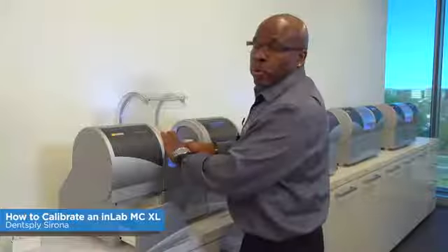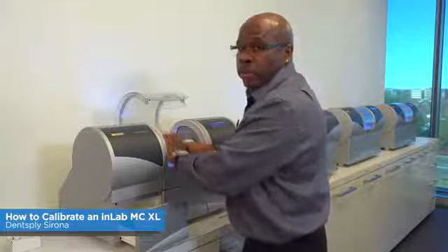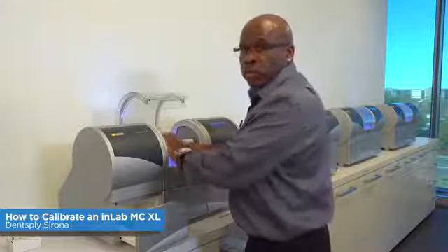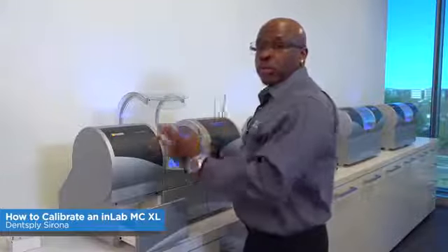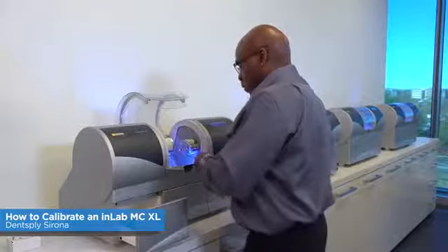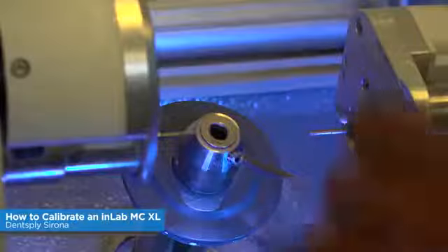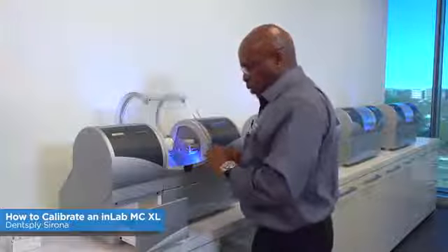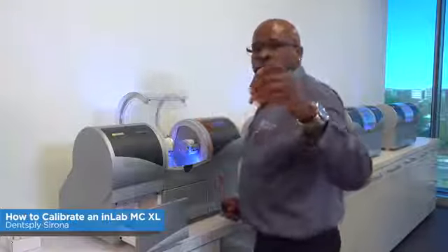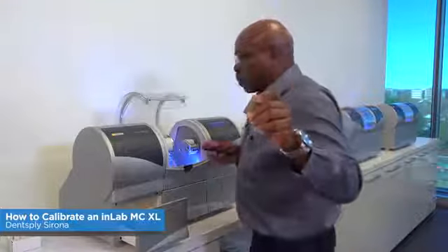What's important at this point is that when you tighten up these calibration pins, you want to make sure this is torqued at least once. You should hear it click. Then I'll take the other torque wrench and remove the sleeve to put the calibration phantom in. So you loosen this screw and pull the sleeve out. What's important is that there's a notch on this calibration phantom. There's a fixer pin at 9 o'clock. When you put this in, it should go into that pin and it shouldn't move. And then you take the torque wrench, tighten it up, and it should click.